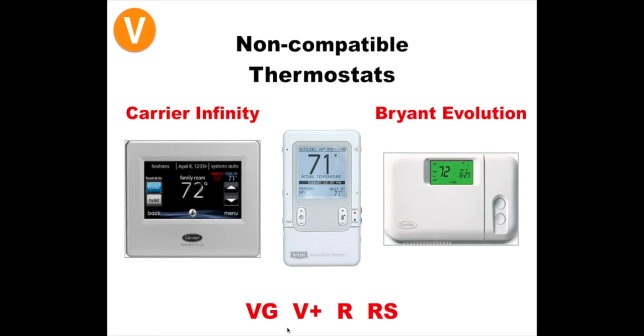So again, identifying these types of thermostats is going to come down to the terminals. On these, they like to use terminals that are labeled VG, V+, R, RS. It can be all sorts of different combinations of these. Sometimes I've seen these where there's just 2 wires. Sometimes I've seen all 4. So keep in mind that these terminals make it not compatible. We can't take it over.